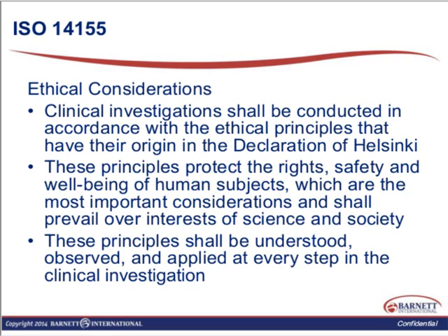So ISO talks about clinical investigations needing to be conducted in accordance with the ethical principles that have their origin in the Declaration of Helsinki, which is the first principle we see in ICH E6. Looking at the protection of rights, safety, and well-being of subjects, the most important considerations over the interests of science and society, is also one of our 13 principles of ICH E6 GCP. The principles need to be understood, observed, and applied at every step in the clinical investigation. So ICH talks about having quality built in, having systems that ensure quality of every aspect of the study.